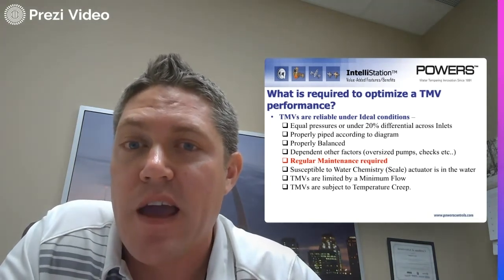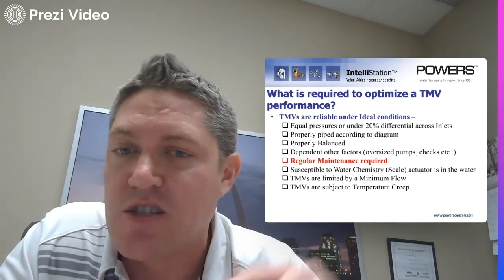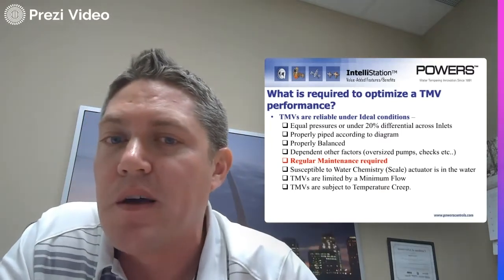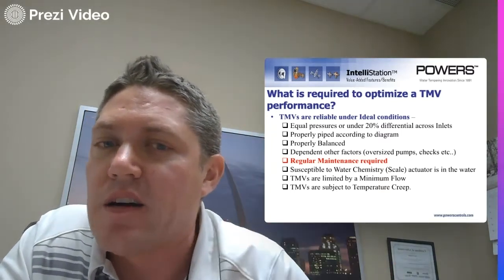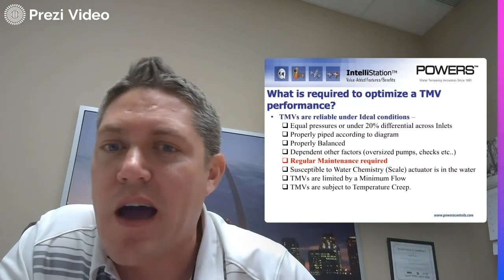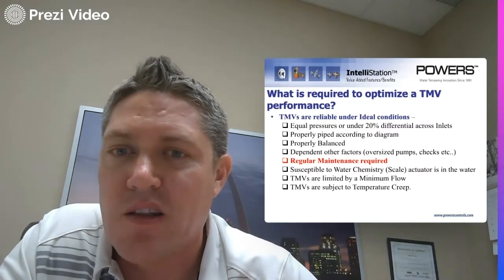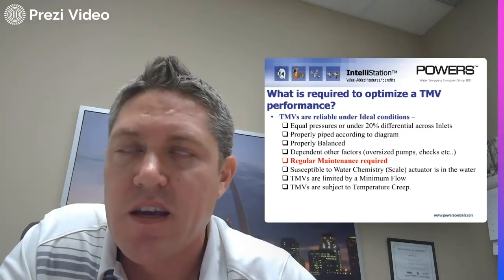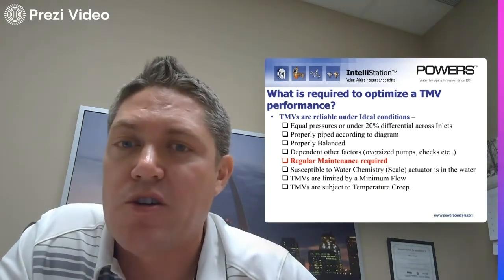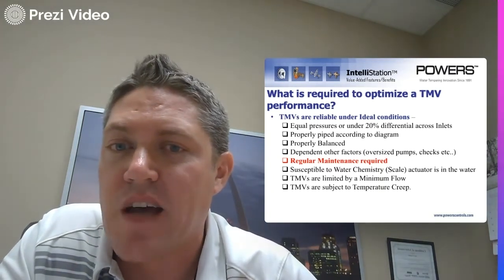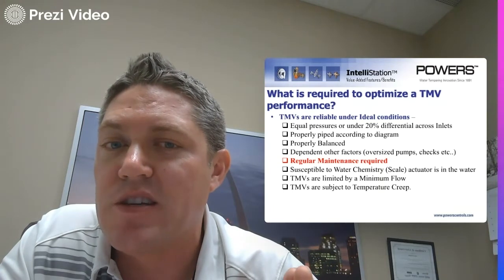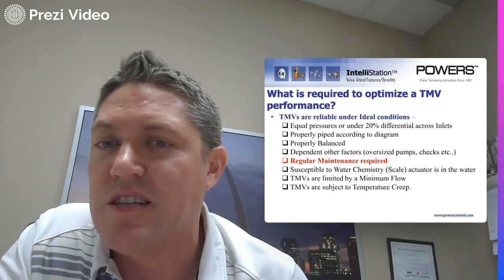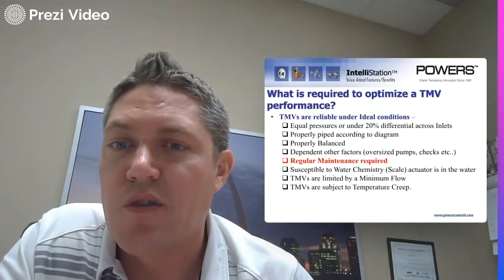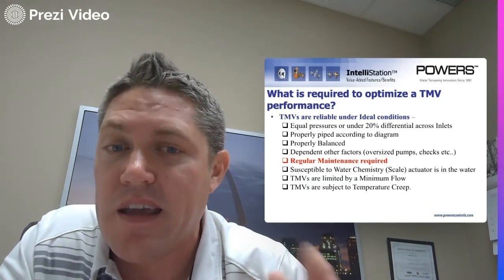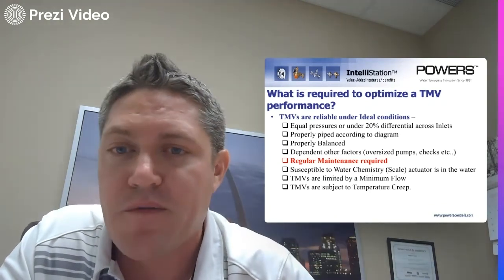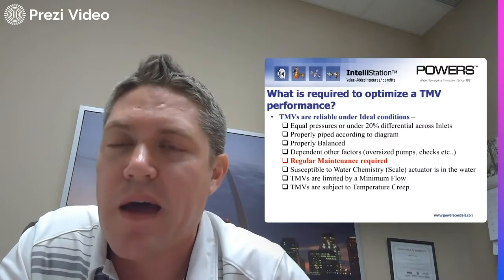Once you're in a no-flow situation, just recircing around in that loop, if you went out at 120 degrees and when you got back there was maybe a 5-degree heat loss and you're at 115, well, most of that return water just needs to go back into the cold side of the mixing valve and back out for the recirc loop. And only a little bit of it needs to go back towards the heater so that it can make up for that heat loss on the loop, that 5 degrees. So very little of it would be going back.